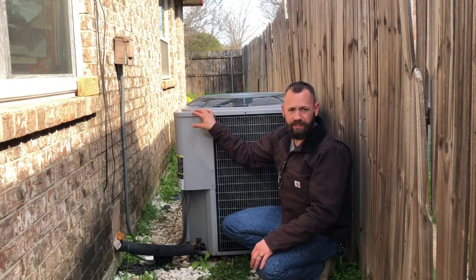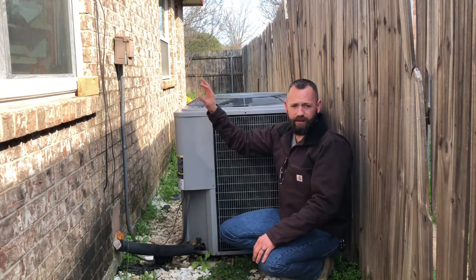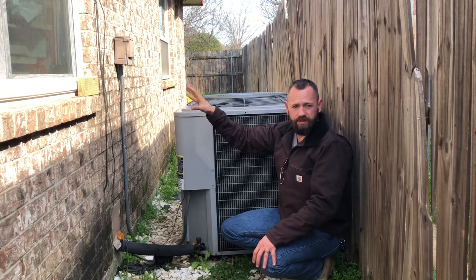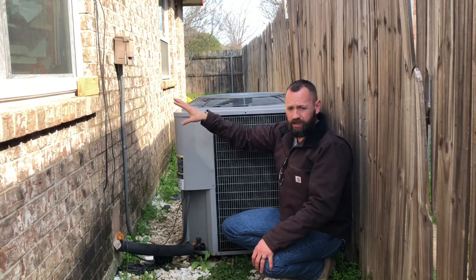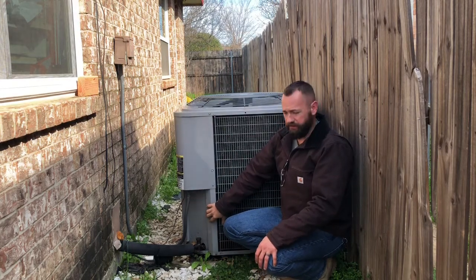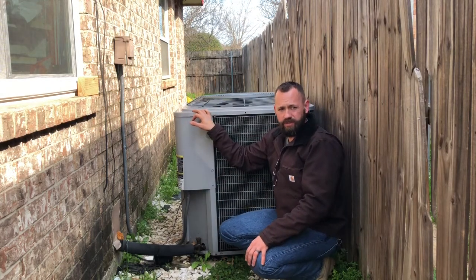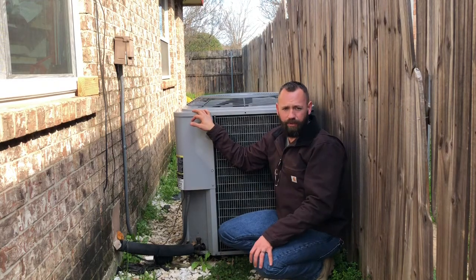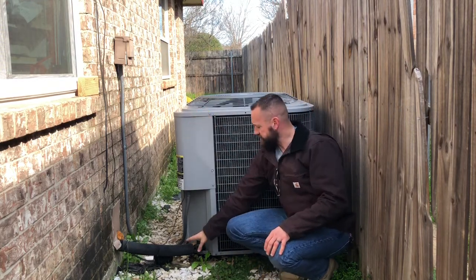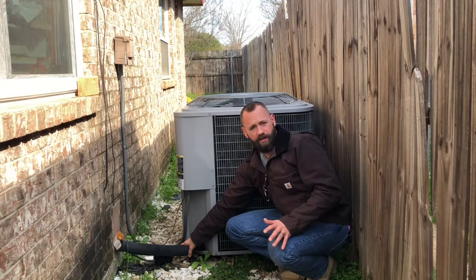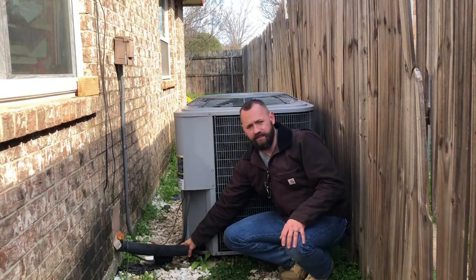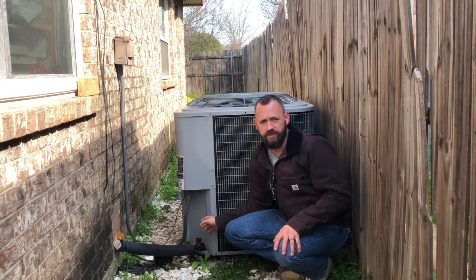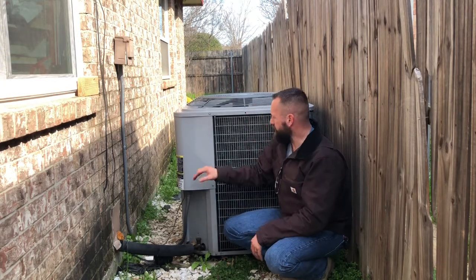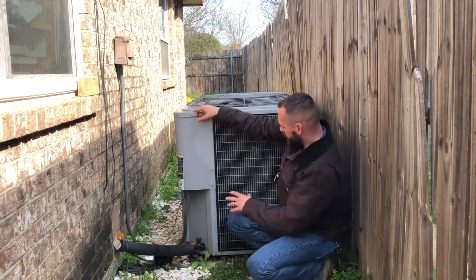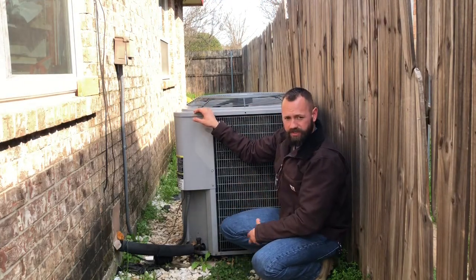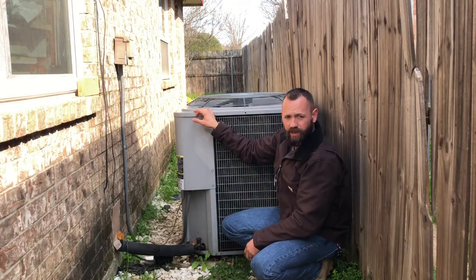This is what we call the condensing unit. So the refrigerant comes from that evaporator coil inside, once it's absorbed the heat from your home to cool off the air, and it brings it out here and condenses it before sending it back up. Remember I showed you the two copper lines going into the evaporator coil upstairs? Well, this is those same two lines outside. So this is connected to that evaporator coil inside. So these two units work together. Now you've got a couple of things going on with this. So behind here is a whole bunch of copper piping that's used in the condensing of the refrigerant.